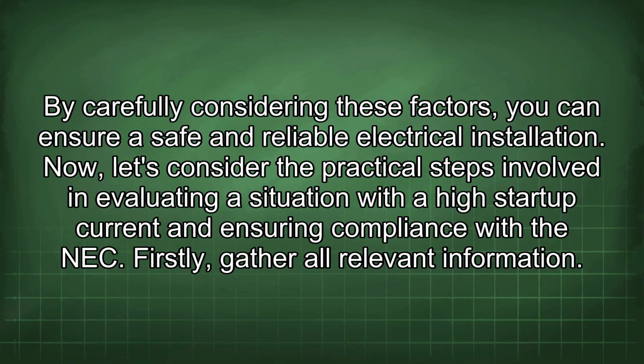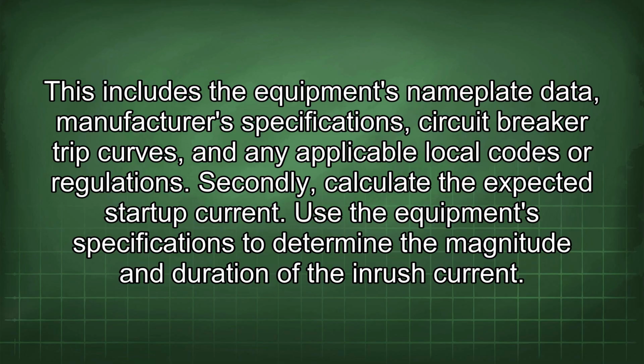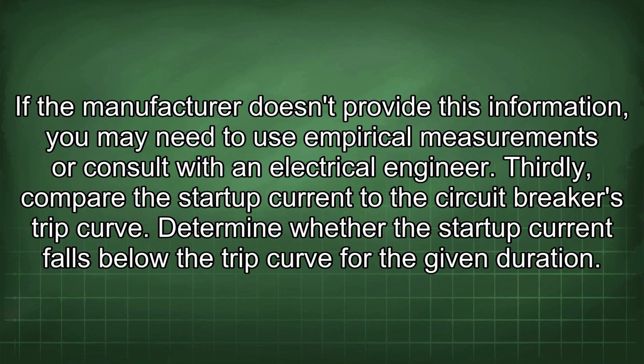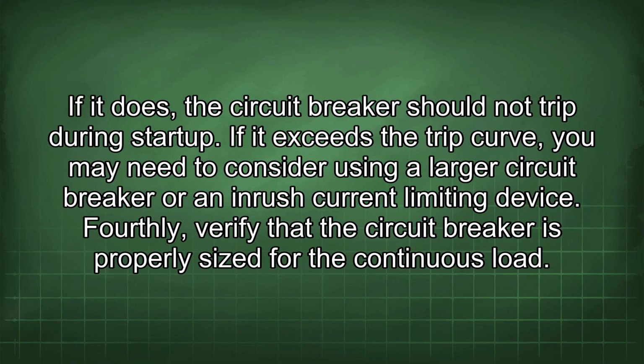Now, let's consider the practical steps involved in evaluating a situation with a high startup current and ensuring compliance with the NEC. Firstly, gather all relevant information. This includes the equipment's nameplate data, manufacturer's specifications, circuit breaker trip curves, and any applicable local codes or regulations. Secondly, calculate the expected startup current. Use the equipment specifications to determine the magnitude and duration of the inrush current. If the manufacturer doesn't provide this information, you may need to use empirical measurements or consult with an electrical engineer. Thirdly, compare the startup current to the circuit breaker's trip curve. Determine whether the startup current falls below the trip curve for the given duration. If it does, the circuit breaker should not trip during startup. If it exceeds the trip curve, you may need to consider using a larger circuit breaker or an inrush current limiting device.